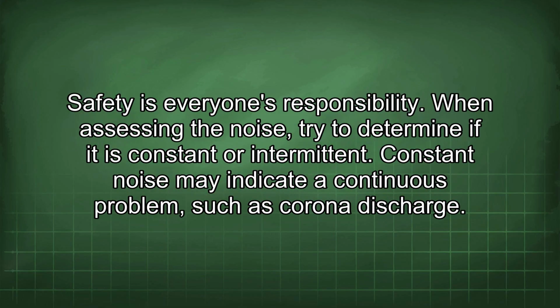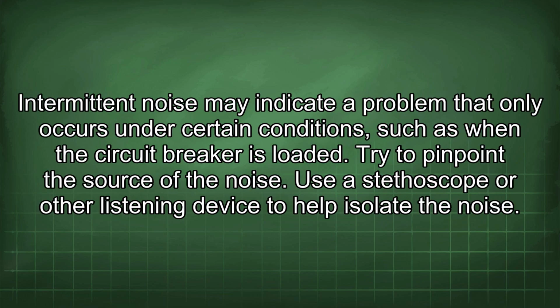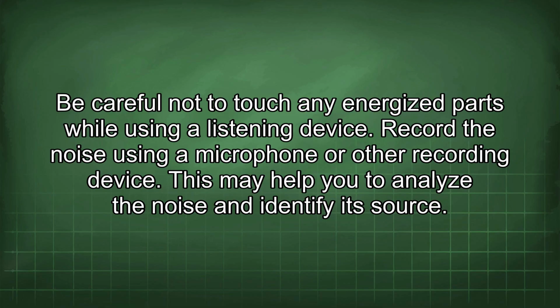Safety is everyone's responsibility. When assessing the noise, try to determine if it is constant or intermittent. Constant noise may indicate a continuous problem, such as corona discharge. Intermittent noise may indicate a problem that only occurs under certain conditions, such as when the circuit breaker is loaded. Try to pinpoint the source of the noise. Use a stethoscope or other listening device to help isolate the noise. Be careful not to touch any energized parts while using a listening device.